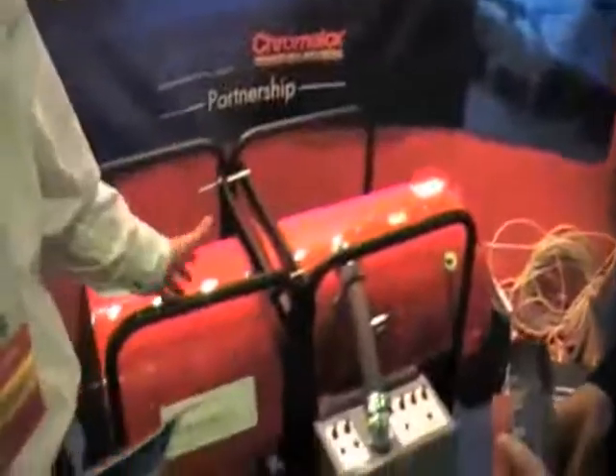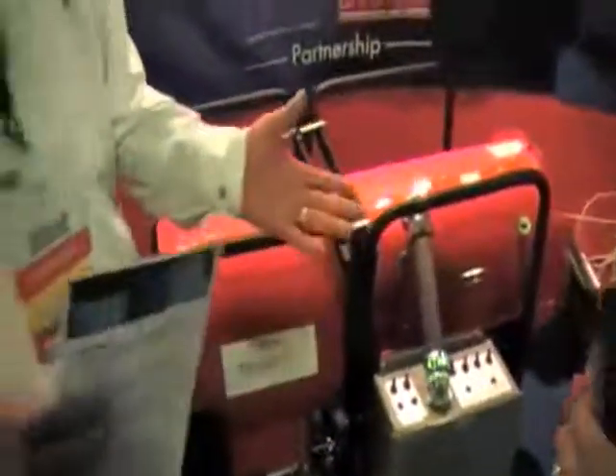And what happens with this is the platform is variable. You can come into a common hotel room, right? Left wall, right wall, bathroom. There's typically 120 volt circuits in that configuration. You look down on the wall where that air conditioning unit is. There's 208 volts there. That's enough power within that room to power up this unit. Worst case scenario, maybe there's only 2 circuits there. You go to the room next door with the power cabling that we provided, and you can utilize power from the room next door to heat that room up.